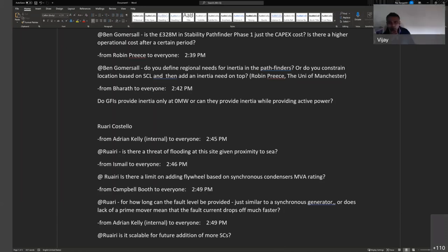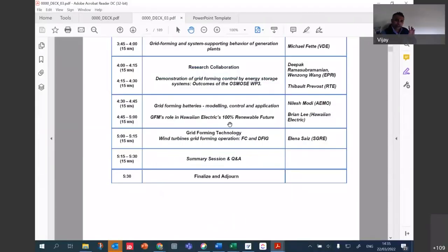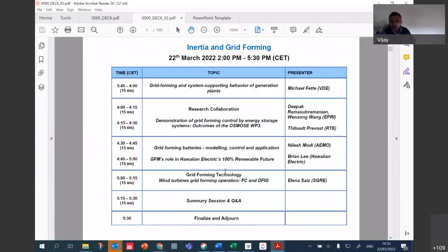One more question, Campbell. Razwan has asked, synchronous condensers usually achieve about 50% of the nameplate rating on the MVAr import absorption side due to the excitation arrangement. Do you have a synchronous condenser solution that can achieve a larger range on the absorption side? Yes, of course we can. One can design the import absorption side, but then you can either compromise on the reactive power MVAr or on the short circuit level. So you will have to make a judgment call depending on what you are looking for. The solution can be designed. Yes. And I'm aware that sometimes synchronous compensators could even be co-located with a STATCOM, so you've got a bit of a hybrid solution for the reactive power specific side of things.